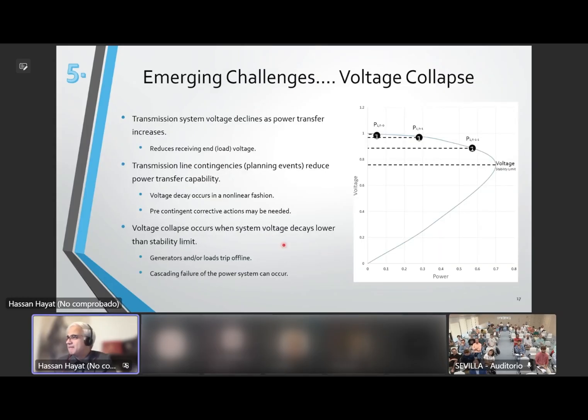We talked a lot about the power carrying capacity, but oftentimes what we're seeing is, as we continue to add load onto the system, we are approaching closer and closer to the knee of the curve. If we add more demand on the grid without taking some additional proactive action, we're going to run into a voltage collapse situation. What that introduces is blackouts. We don't want to be in that situation.